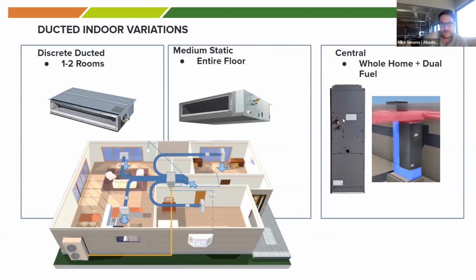One of the nice things about centralized heat pumps is you can build in a little redundancy with the equipment. If the outdoor unit is covered in snow, or there's a snow apocalypse, polar vortex, or any weird weather event, this can also have an electric resistance element that can kick in during those extreme weather events. So there's a lot of flexibility regarding design: wall mounts, floor mounts, ceiling mounts, or ducted. There's usually a way to adopt air source heat pumps.